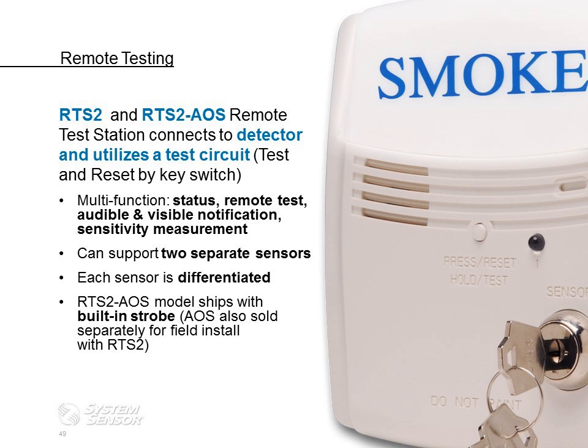This product can support two separate sensors. When you do the 2-to-1 configuration that we talked about earlier, you can maintain and test both of those heads separately using one remote test accessory. That saves you the cost of an additional remote test and indication accessory. The RTS2 AOS model ships with a built-in strobe. The AOS is also sold separately if you need to field install with an RTS2. If you need to upgrade a standard RTS2 to an AOS, you can do that. It's just a plug-and-play board.